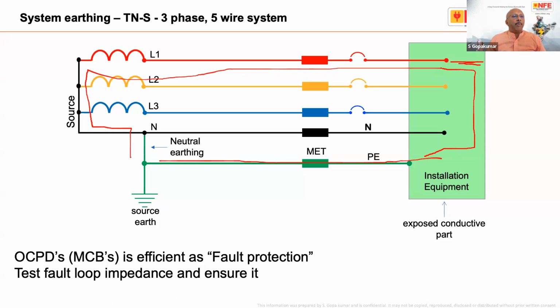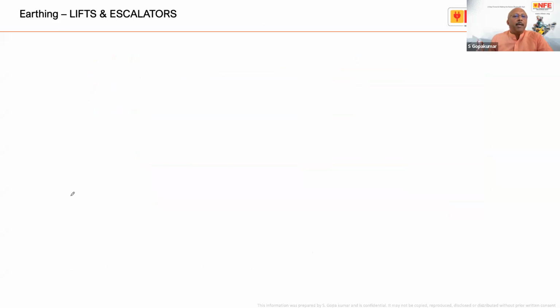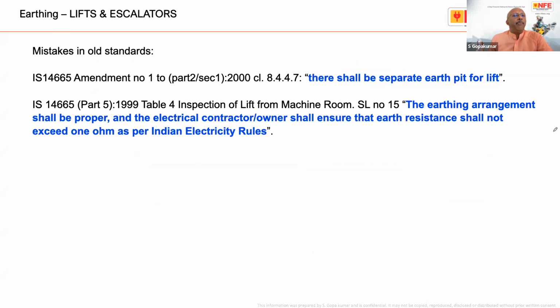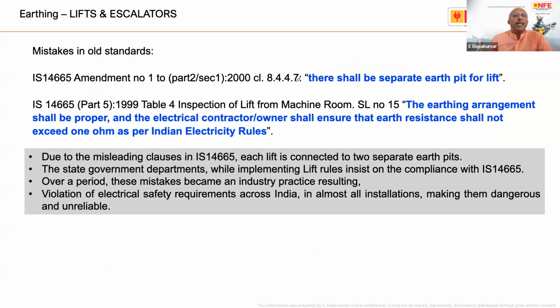So we have to put our efforts to ensure that the DISCOM is giving this kind of supply, or the electrical inspectorate or the lift inspectors are demanding this kind of supply. Only then can the installation be made reliable. Actually, in my view, if we look at the standard, these two clauses, I would say it's a mistake. This one, 8.4.4.7, is a clear mistake. Nowhere is this kind of requirement there.